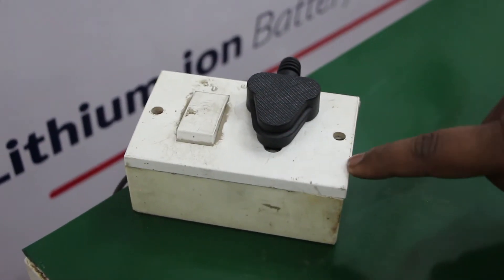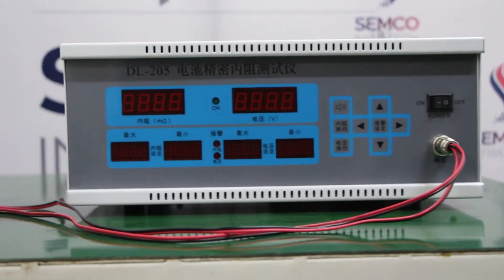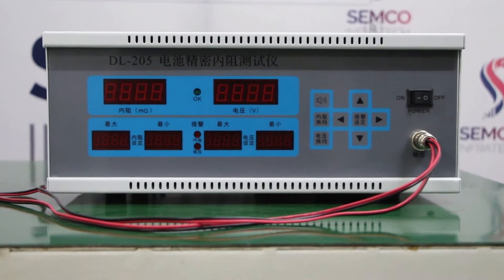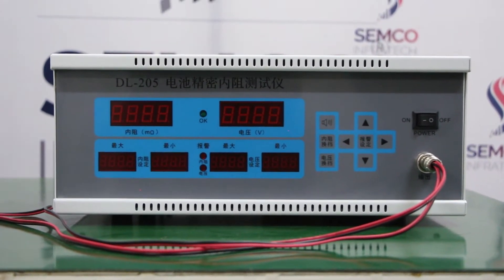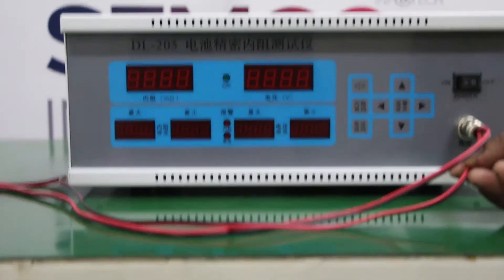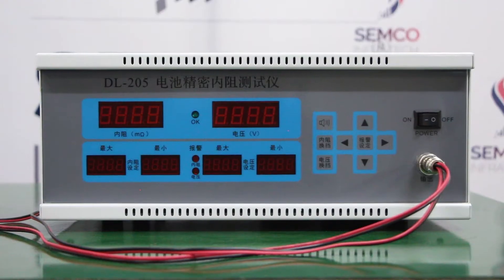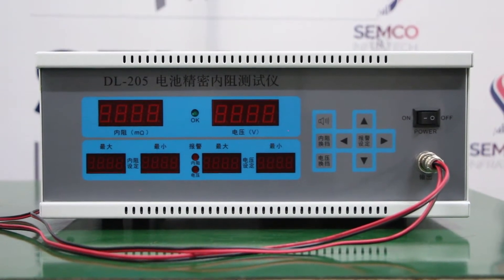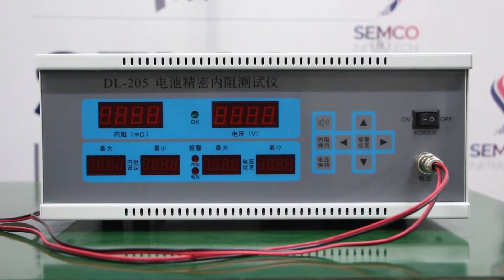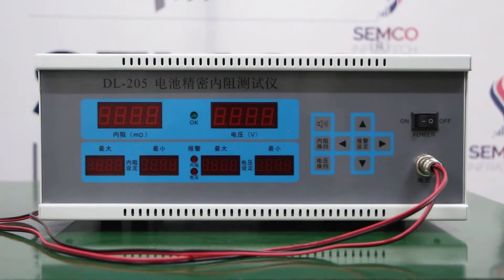This machine is operated at 220V single phase AC. The battery internal resistance tester is a new type of instrument that uses alternating current to test the internal resistance of a battery. It also tests the voltage of the battery at the same time, using 4 wires for effective elimination of error. This tester can also set alarms for unqualified values of batteries — unqualified resistance and unqualified voltage — according to their battery needs.